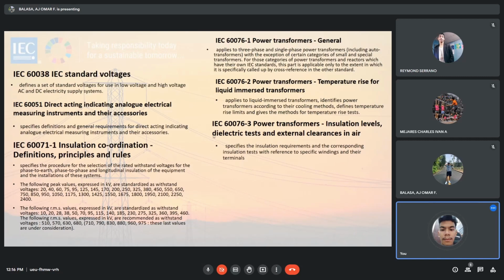wave shape of supply voltage, a supply voltage of which the wave shape is approximately sinusoidal. This requirement is normally not critical in public supply systems, but may have to be considered in installations with considerable converter loading. In such cases, there is a conventional rule that the deformation shall not exceed 5% of total harmonic content nor 1% of even harmonic content. Also note the importance of current harmonics for load loss and temperature rise.